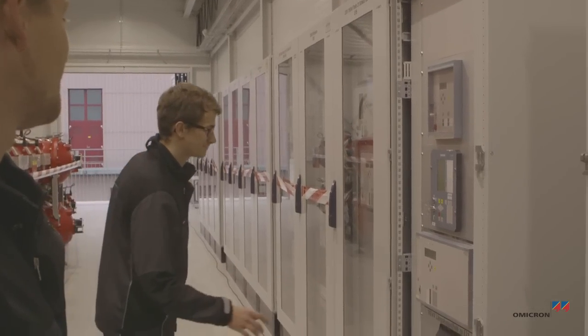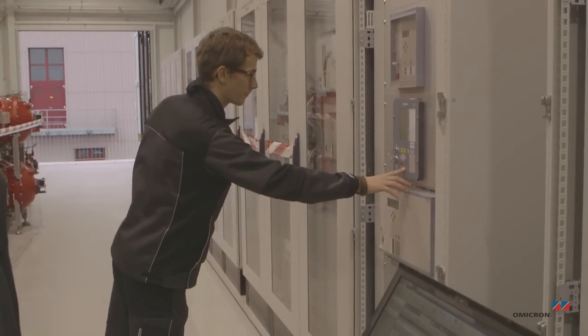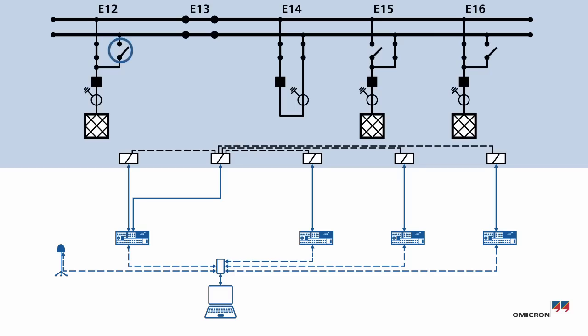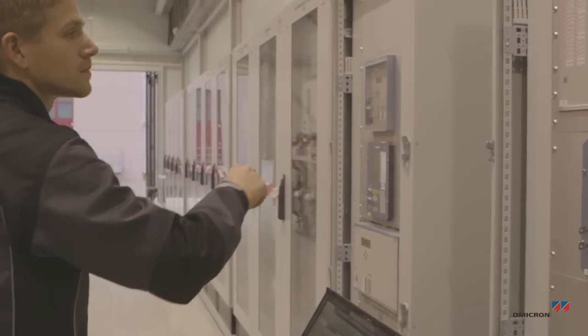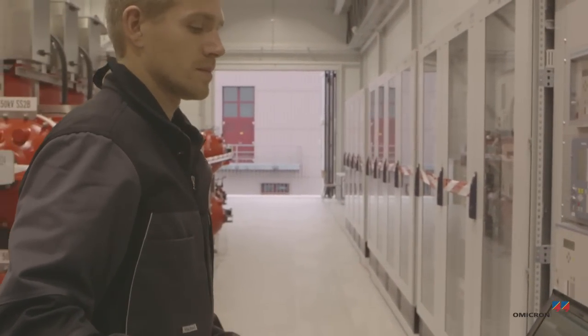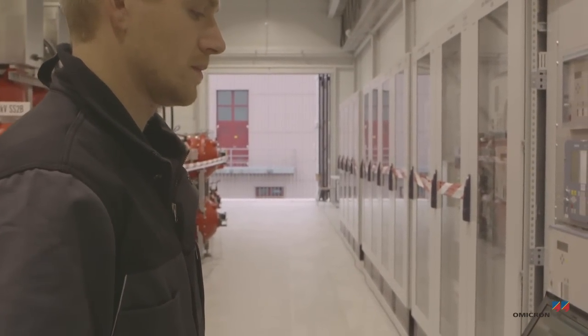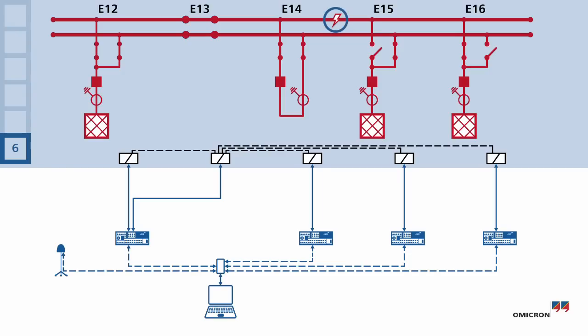By closing the second isolator of one of the bays, Johannes links the two bus bars to one another. Florian checks to see if the protection can also handle this case correctly.